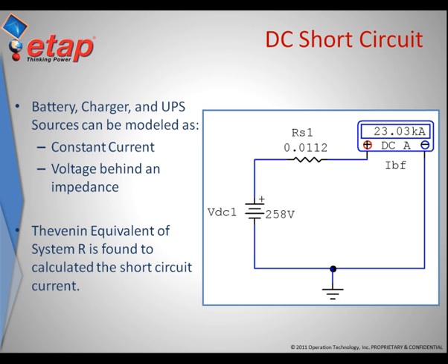These sources can be modeled as either constant current or voltage behind impedance sources. The typical modeling in DC short circuit calculations is to represent these sources as Thevenin equivalents using their equivalent resistance and internal voltage to determine the amount of short circuit to a fault. As can be seen in this slide, the available DC short circuit current for a fault in this circuit is 23.03 kilo amps, with a voltage source of 258 volts DC and a system impedance of 0.0112 ohms.